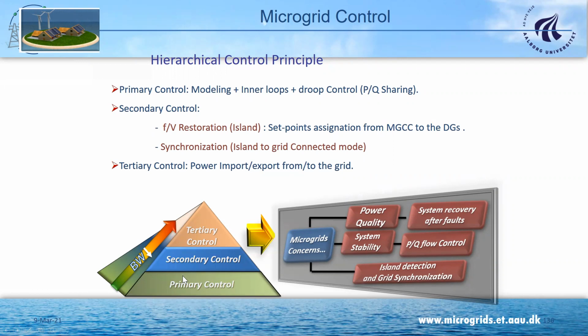However, since we don't have inertia, in the primary level we have to add that inertia with local controllers. In the secondary control it's a bit different, because active power, when you go to more resistive lines, is more connected to voltage than to frequency. So here the secondary control needs to take care not only of the frequency, but also the voltage.